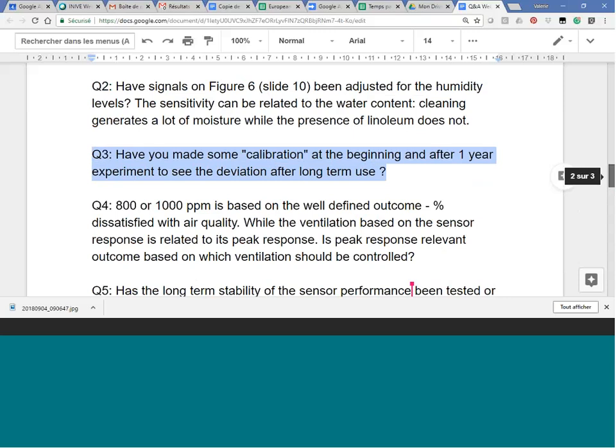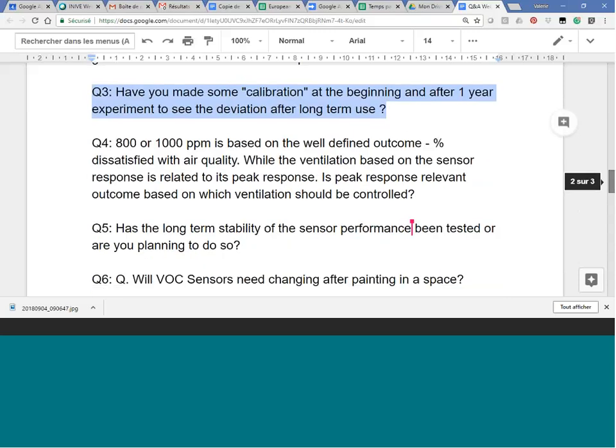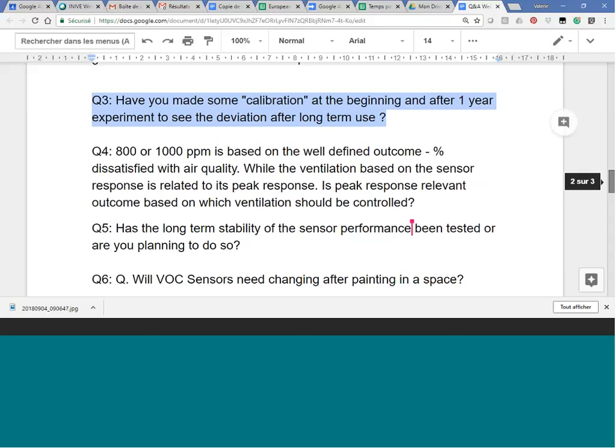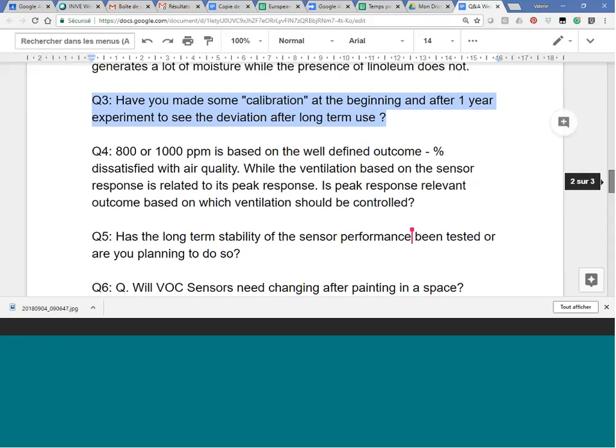The calibration itself is an issue. Some of the producers recommend a calibration, but then it's a question about what you use for calibration. They calibrate the sensor, or they claim in some of the data sheets you can read that they calibrate the sensors with isobutanol, acetone, single compounds, but this does not say that your sensor is calibrated when.